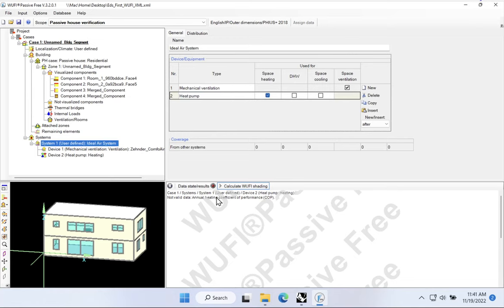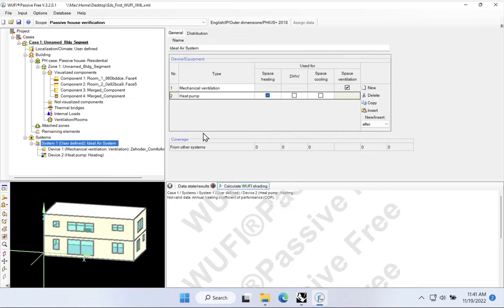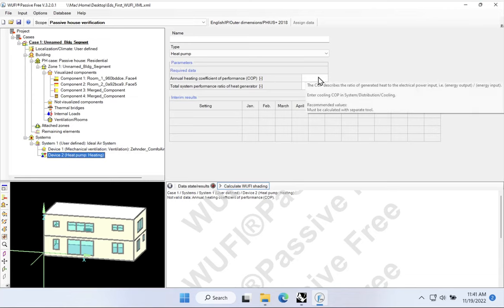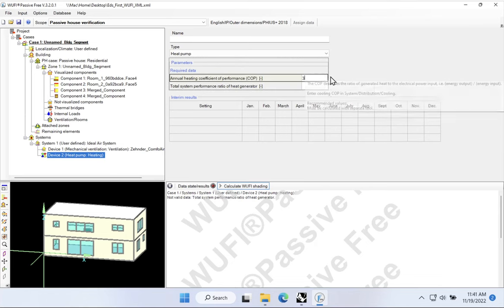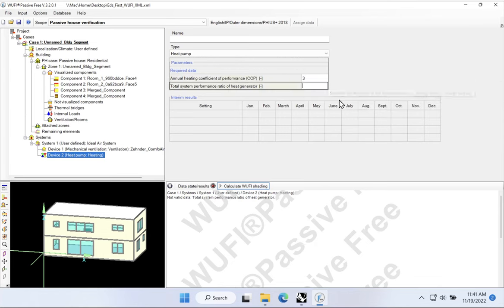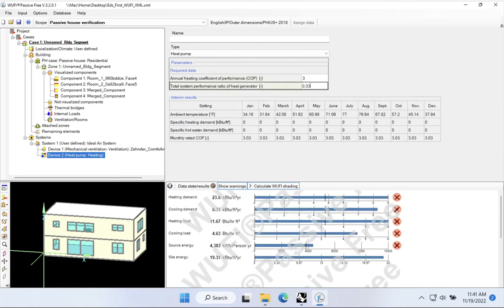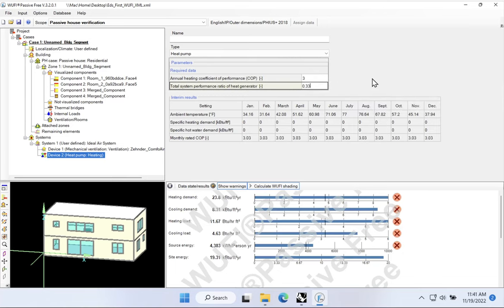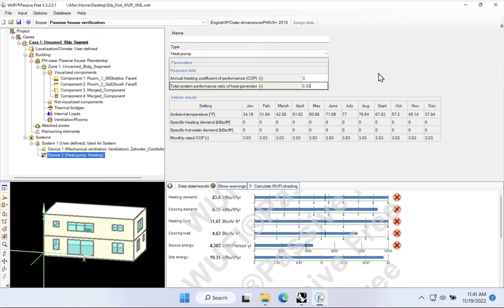Now, WUFI's going to start complaining at this point. It's going to say you said you're using a heat pump, but you haven't given me enough data for me to accurately calculate the overall performance of the building. So one of the things we would have to do is come over here to our heating system, our new heating system, and we would have to give it some information. So what's the COP? I don't know, 3. What's the system performance ratio? 0.33, the inverse, typically the inverse of the COP.